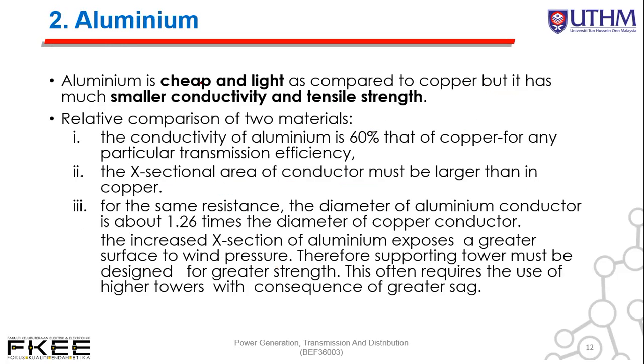Second is aluminium. Aluminium is cheaper than copper and also light compared to copper, but it has small conductivity and small tensile strength. In relative comparison between these two materials, the conductivity of aluminum is 60% that of copper. The cross section area of conductor must be larger than in copper. This means that the cross section area of aluminum is larger. For the same resistance, the diameter of aluminum conductor is about 1.26 times the diameter of copper conductor.